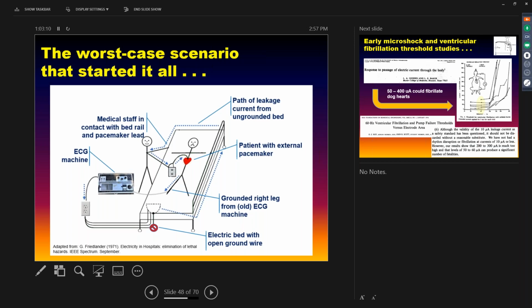So you got a patient here in a bed, electric bed. You remember the older beds, virtually all metal, guardrails all metal, electric bed. The old electrocardiographs in that era, it was not uncommon for the right leg to be grounded, earth to ground, or very, very close to earth to ground. And the patient had an indwelling cardiac pacemaker cath, a wire right into the heart, coming out into a box. So the scenario was, and that would not be atypical back in that era, a patient in a bed with an external pacemaker hooked up to the ECG machine.